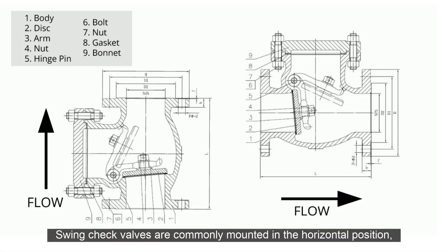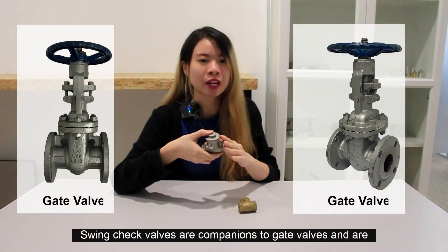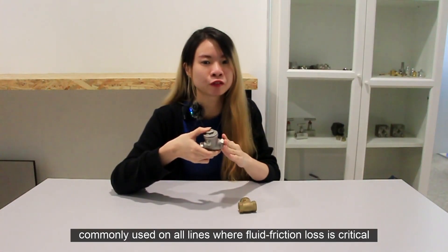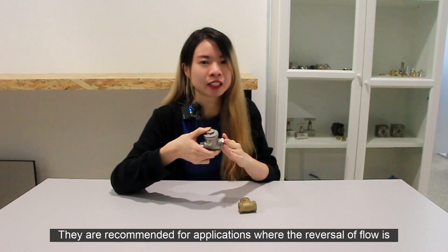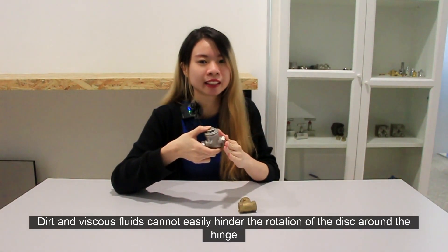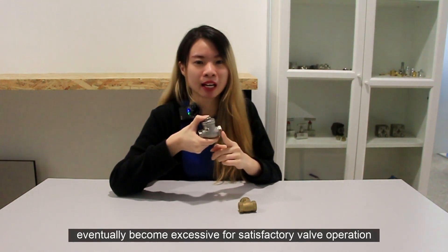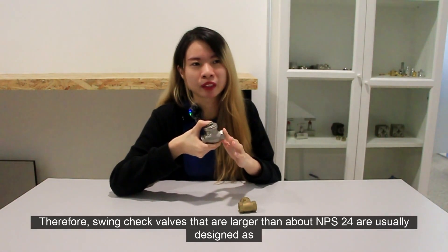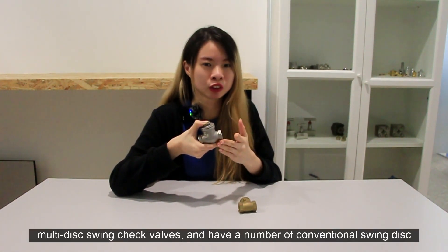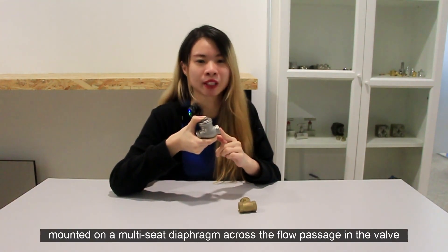Swing check valves are commonly mounted in a horizontal position, but some may be mounted in a vertical position, provided the disc is prevented from reaching the stopping position. Swing check valves are the companion to gate valves and are commonly used in lines where fluid friction loss is critical. They are recommended for applications where reversal of flow is not frequent, to prevent valve chattering. Thick and viscous fluid can easily hinder the rotation of the disc around the hinge. As the size of the swing check valve increases, the weight and inertia of the disc can become excessive for satisfactory valve operation. Therefore, swing check valves larger than about NPS 24 are usually designed as multi-disc swing check valves, with a number of conventional swing discs mounted on a multi-seat diaphragm across the flow passage in the body.